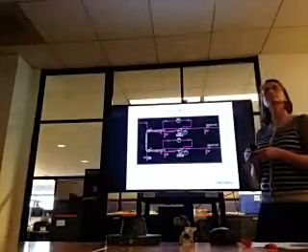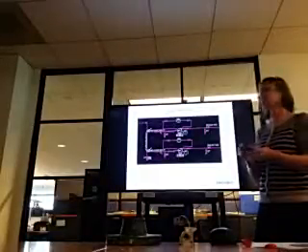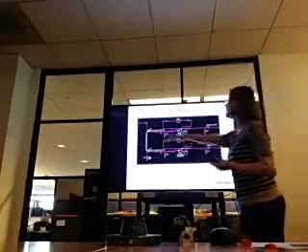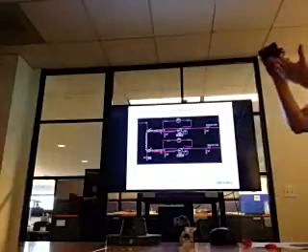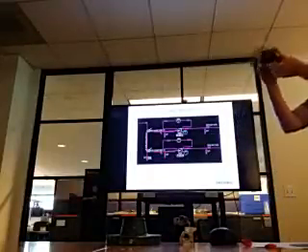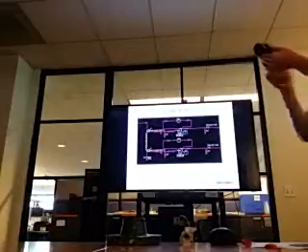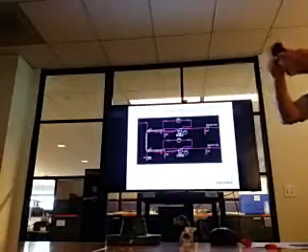So when you isolate it, you end up relieving the pressure in there, and then you end up doing a service on that. So we prefer not to just put a plug here. And what Steve was saying is exactly what we show here on the P&ID. We would just have a little piece of pipe. A little piece of pipe is called just a nipple. We put a threaded nipple in here, put a ball valve here, and then put a plug on the end of the valve, because then we can just take the plug off and then open the valve. And then if we need to shut it off, we can shut it off very quickly.